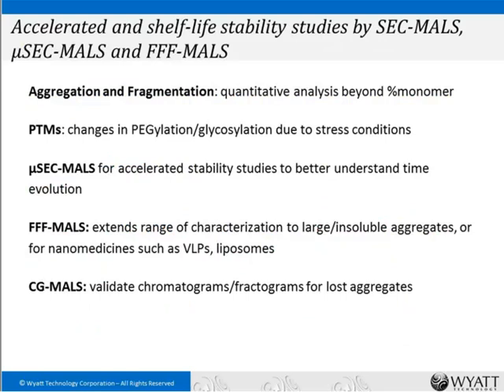To summarize the accelerated and shelf life stability studies stage: by extracting aliquots and running them through SEC-MALS, microSEC-MALS, or FFF-MALS, you can assess aggregation and fragmentation and other degradation types, giving quantitative analysis beyond simple percent monomer. You can assess post-translational modifications and how they change under stress. MicroSEC-MALS using UHPLC enables higher-frequency time points. FFF-MALS extends characterization to large and insoluble aggregates and is also useful for species not amenable to SEC — nanomedicines, VLPs, liposomes, and so forth.